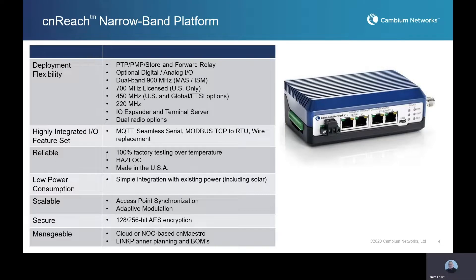Cambium's solution is called CN Reach. It's a narrowband platform that operates in multiple frequencies. In the unlicensed spectrum, we work in the 900 megahertz ISM band, and then also a number of licensed frequencies: 900, 700, 450, and 220 megahertz bands. In those licensed bands, oftentimes you're working with a 12.5 kilohertz or 25 kilohertz channel — very narrowband applications and low capacity.